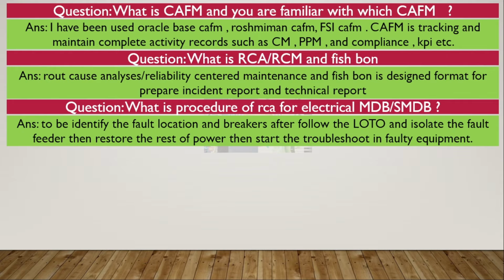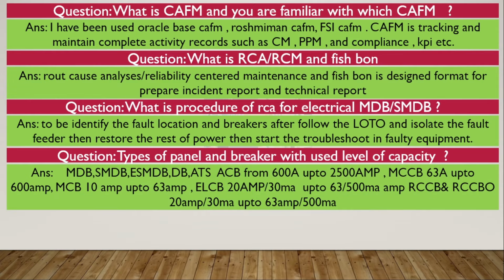What is the procedure of RCA for electrical MDB and SMDB? Root cause analysis for electrical: identify the fault location and the breaker, follow LOTO and isolate the fault feeder, then restore power to the rest, then start troubleshooting the faulty equipment. Also know the type of panel and breaker with usage level and capacity. Types of panel: MDB, which is main distribution board, SMDB, sub-main distribution board, ESMDB, essential sub-main DB board, DB, distribution board, and ATS, auto transfer switch. These are the types of panel.